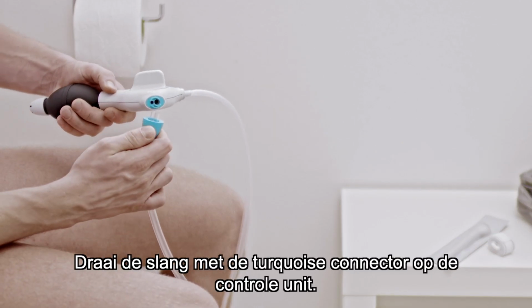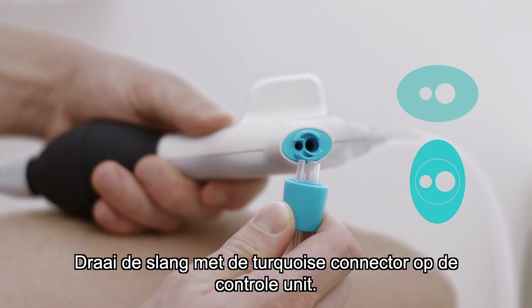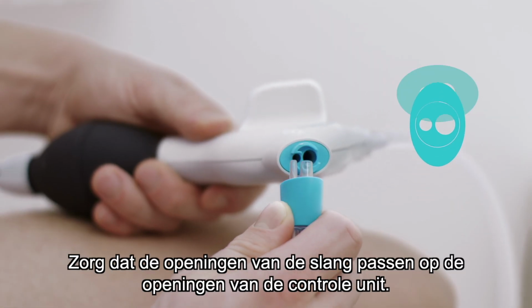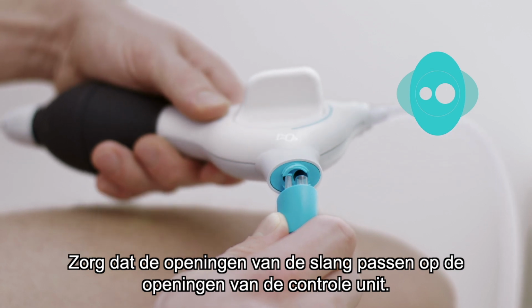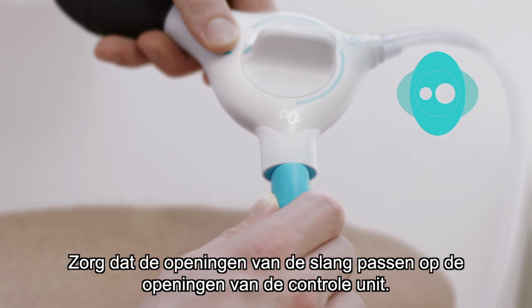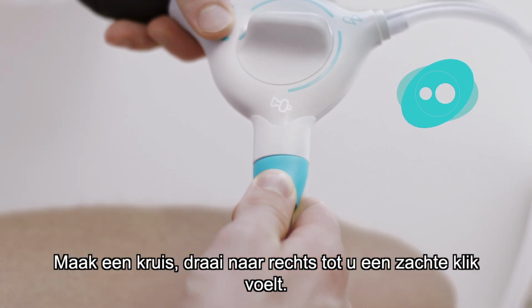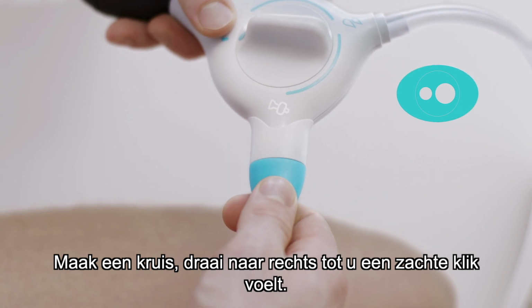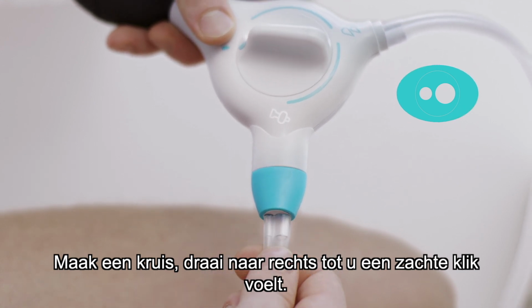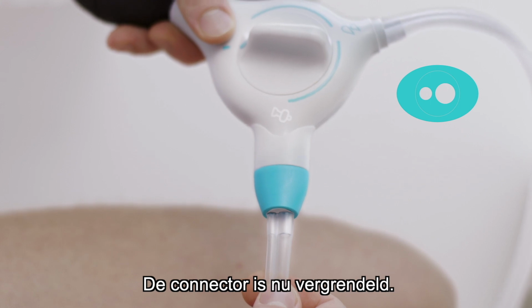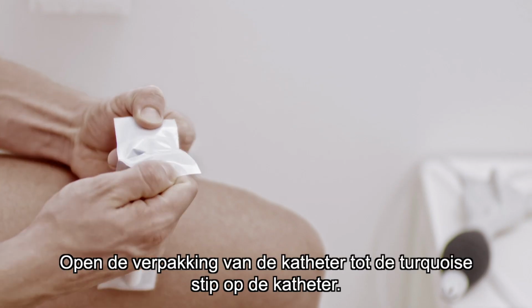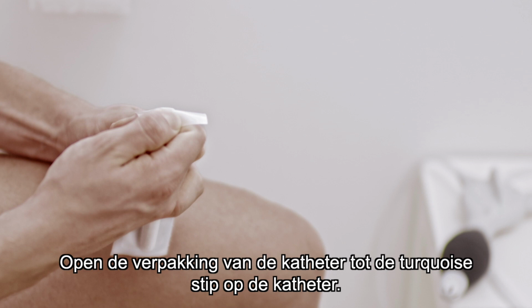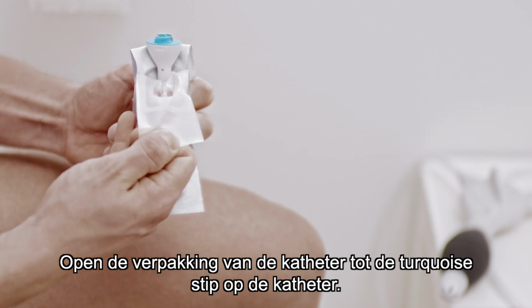Attach one end of the tube with the turquoise connector to the control unit. Align the big tube with the big hole and the small tube with the small hole. Make a cross, and then twist the connector clockwise until you feel a subtle click. The connector is now locked. Now slightly open the balloon catheter packaging to the turquoise dot on the catheter.